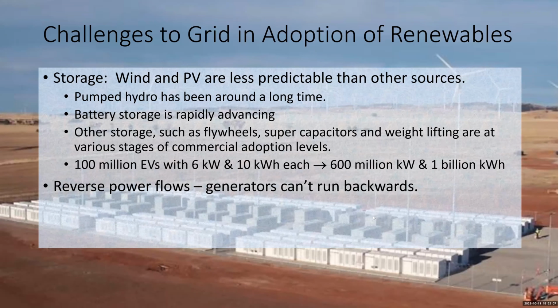We're looking at challenges to the grid. Another challenge is not just storage, but if you have so much renewable generator energy available that it exceeds the demand of the load, it wants to go somewhere. It might want to go to the generators themselves, the big 500 megawatt utility generators. And if you've got reverse power flow going to that generator, that means it wants to turn it into a motor, and the prime movers don't appreciate that at all. So most power plants are protected from reverse power flows anyway. The bottom line is either you have to curtail your renewable source or you have to store it, and generally storage is the more cost-effective solution.